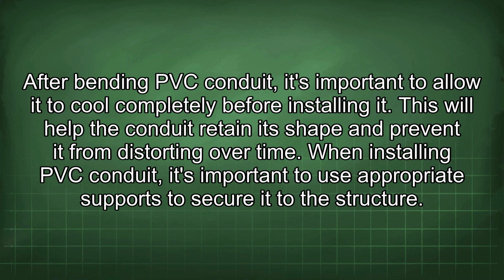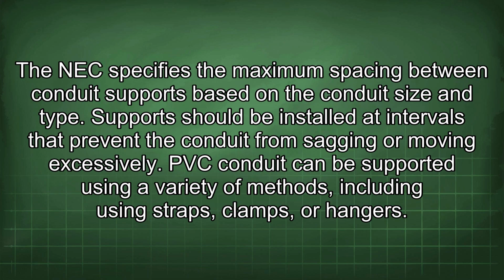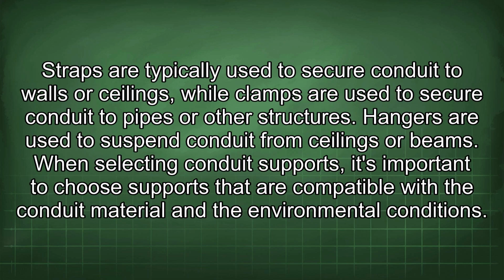When installing PVC conduit, it's important to use appropriate supports to secure it to the structure. The NEC specifies the maximum spacing between conduit supports based on the conduit size and type. Supports should be installed at intervals that prevent the conduit from sagging or moving excessively. PVC conduit can be supported using a variety of methods, including using straps, clamps, or hangers. Straps are typically used to secure conduit to walls or ceilings, while clamps are used to secure conduit to pipes or other structures. Hangers are used to suspend conduit from ceilings or beams.